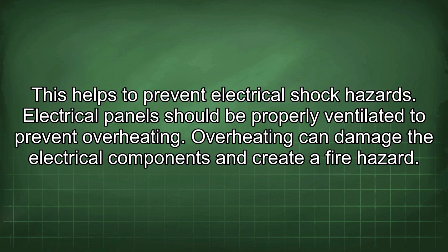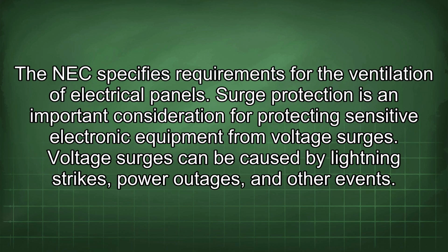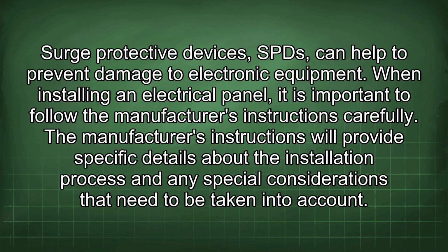Electrical panels should be properly ventilated to prevent overheating. Overheating can damage the electrical components and create a fire hazard. The NEC specifies requirements for the ventilation of electrical panels. Surge protection is an important consideration for protecting sensitive electronic equipment from voltage surges. Voltage surges can be caused by lightning strikes, power outages, and other events. Surge protective devices, SPDs, can help to prevent damage to electronic equipment.